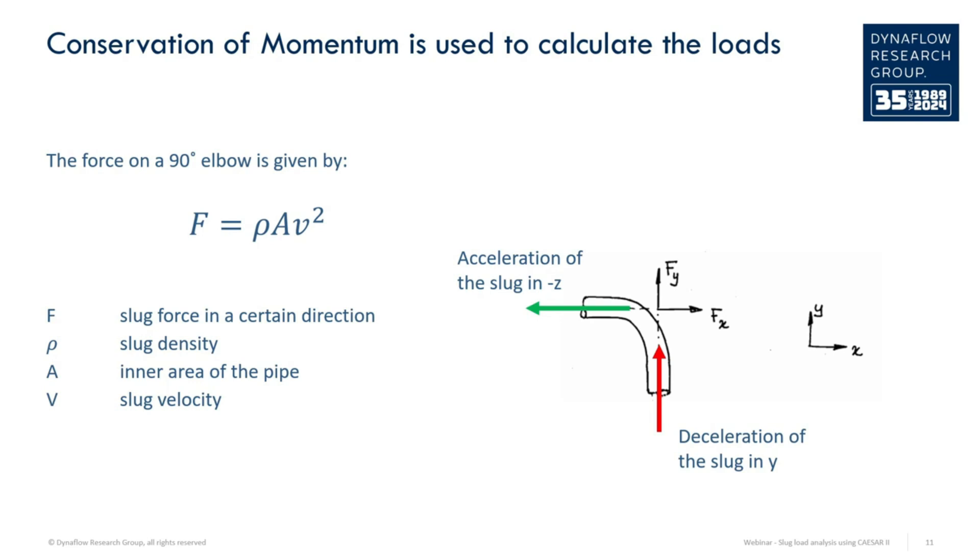The formula for the force on the elbow is therefore F equals rho times A times V squared, or force is equal to the density multiplied by the inner pipe area and the velocity of the slug squared.